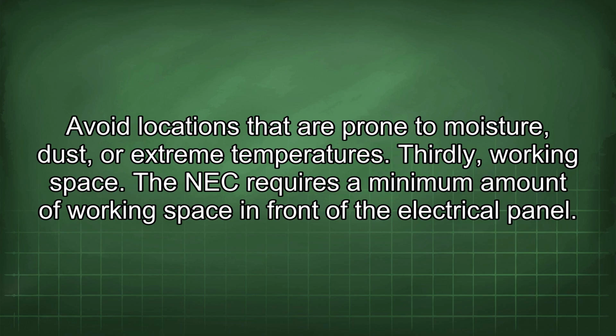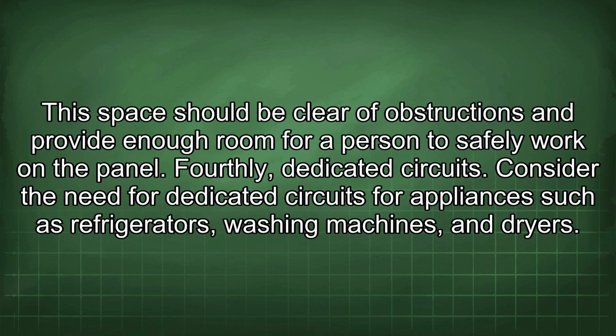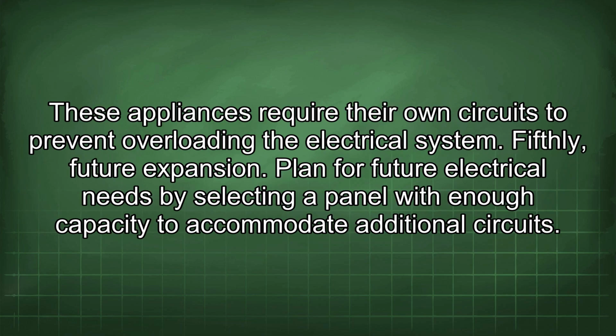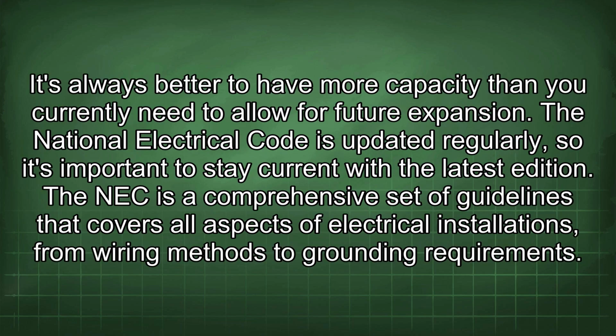Thirdly, working space. The NEC requires a minimum amount of working space in front of the electrical panel. This space should be clear of obstructions and provide enough room for a person to safely work on the panel. Fourthly, dedicated circuits. Consider the need for dedicated circuits for appliances such as refrigerators, washing machines, and dryers. These appliances require their own circuits to prevent overloading the electrical system. Fifthly, future expansion. Plan for future electrical needs by selecting a panel with enough capacity to accommodate additional circuits. It's always better to have more capacity than you currently need to allow for future expansion.